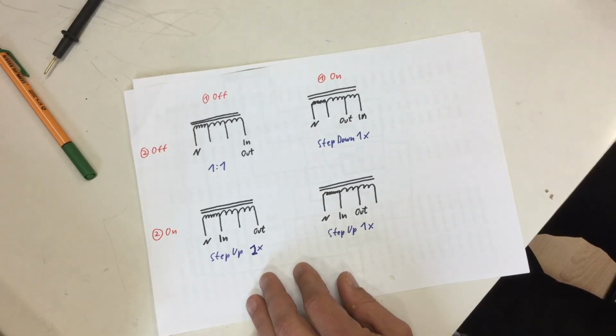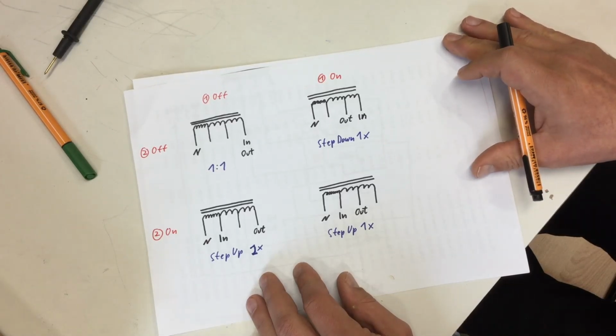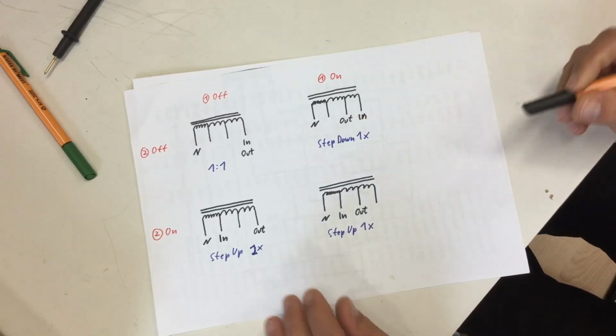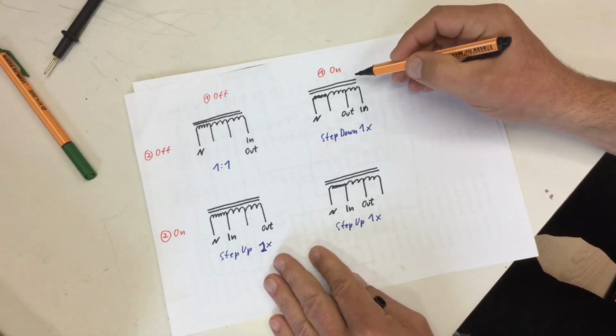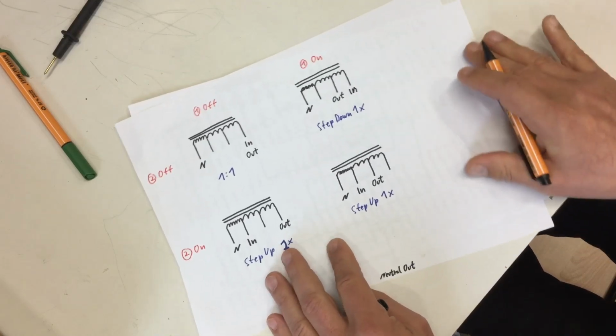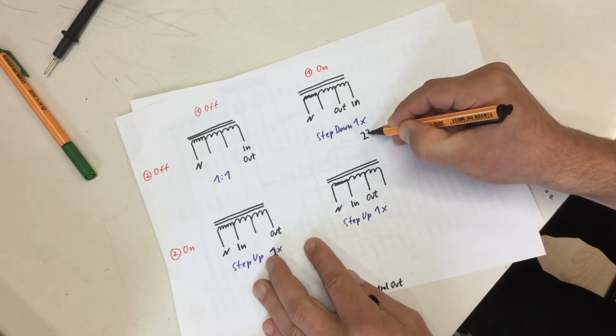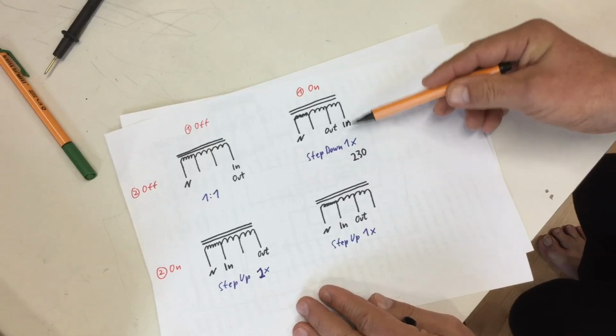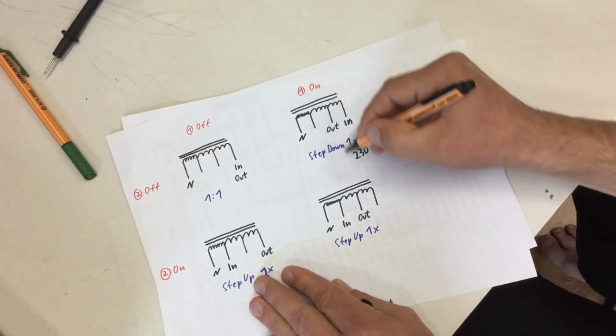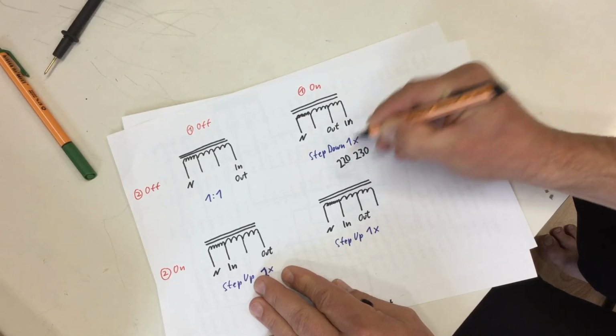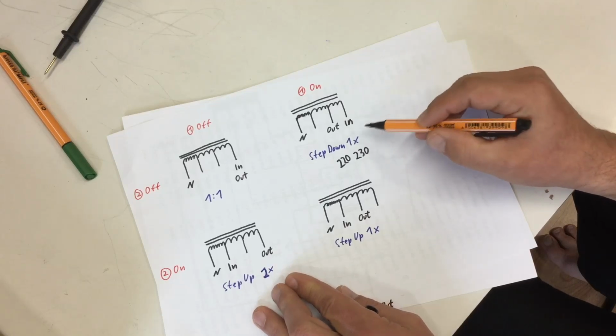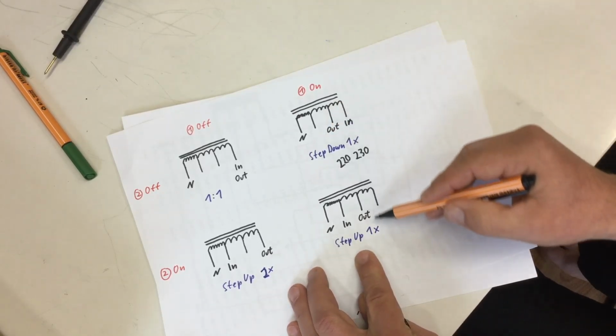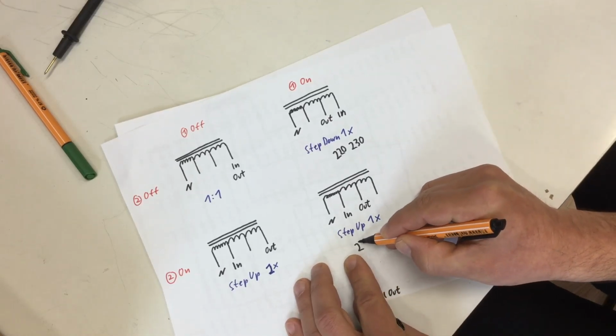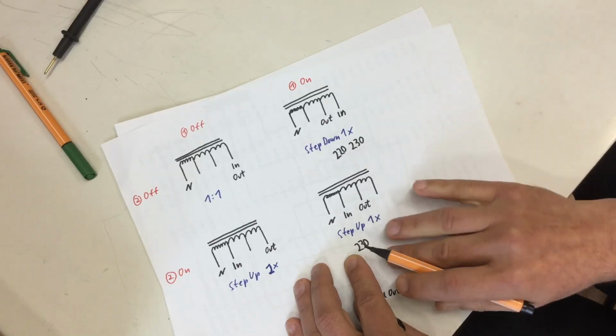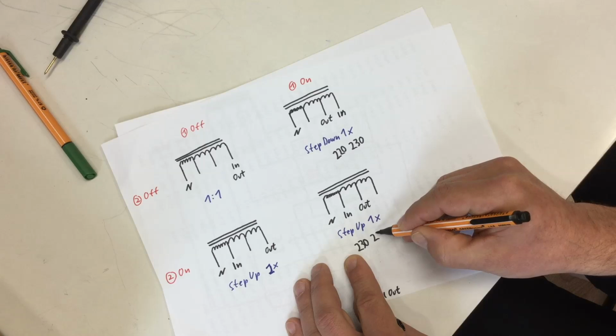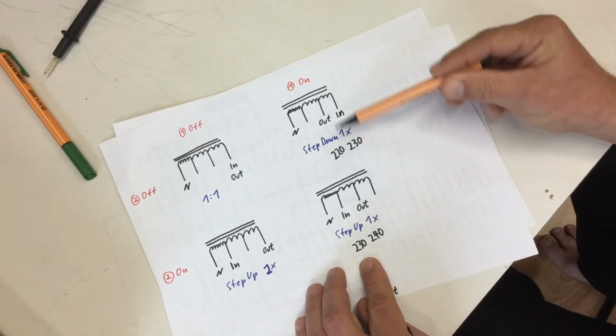I found one hint in the manual, and it says if you have, on the 230 volt models for Europe, if you put the input at 230 volts, you can, within the options of the device, say you want a fixed output voltage of 220 volts. And I guess that's one step down. And if you have again 230 volts, you can also step up, fixed output voltage to 240 volts. I guess that's to accommodate different equipment.